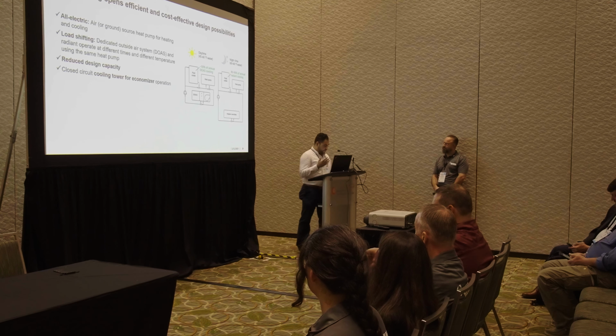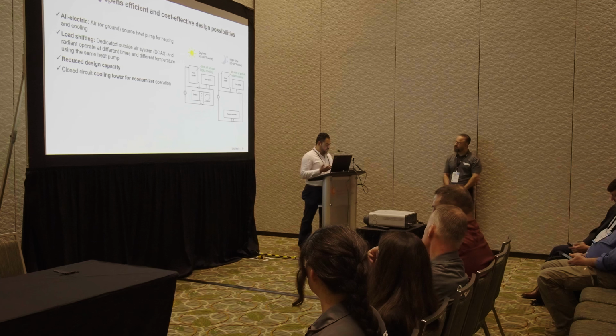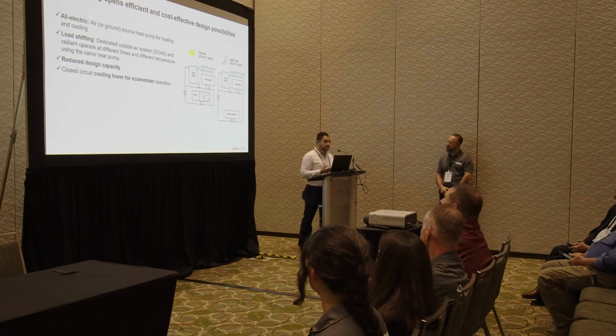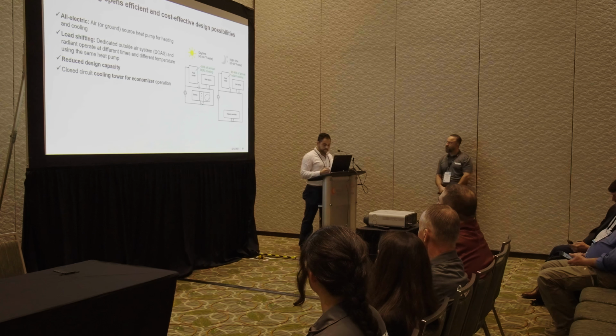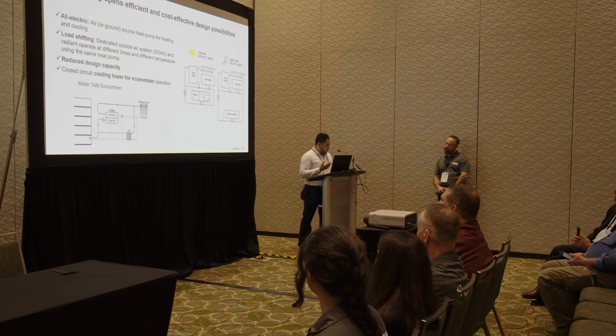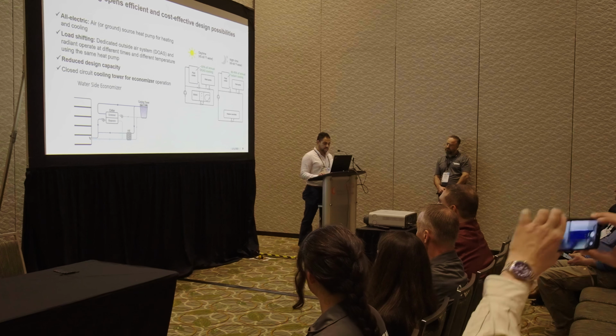Or we can design innovative systems that you can see here on the right-hand side. So where we can use a heat pump to provide the energy source for a DOAS system, and then use that same heat pump to provide the energy source for the radiant systems at other times of the day. So the same heat pump, lower capacity, providing the energy source for the two systems, and they're not operating at the same time. And this kind of system also allows us more possibilities in which we can use water side economizing to provide the cooled water, and thus further increasing the energy performance of this type of system.